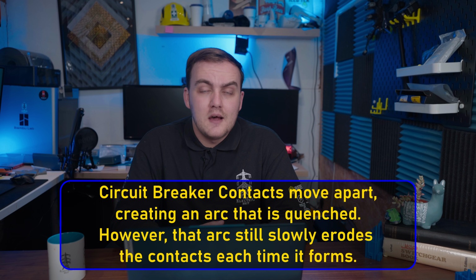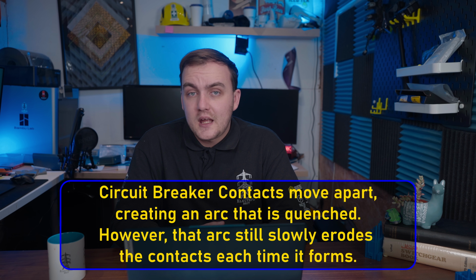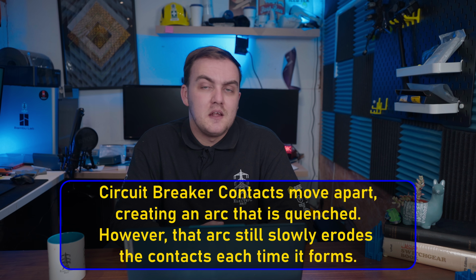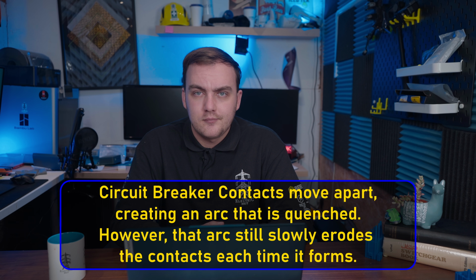The contacts themselves need to be replaced every so often, as they regularly take a beating from the arcs and degrade away, and that gap between the contacts needs to be carefully maintained to work effectively. And the biggest concern with anything oil filled is maintaining the oil, making sure it's topped up and has the right amount to quench arcs and dissipate the heat, making sure the oil is regularly serviced to remove any contaminants like moisture and build-up of breakdown products like carbon, which accumulates every time an arc is drawn.